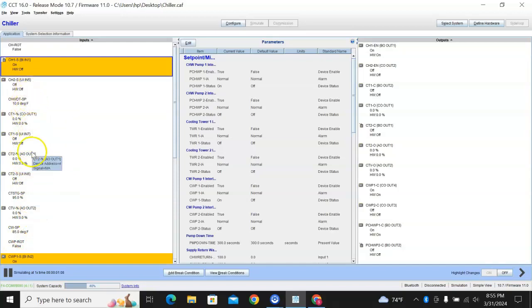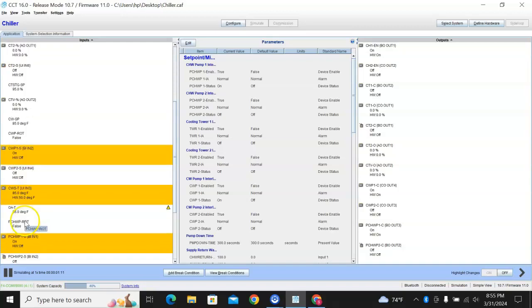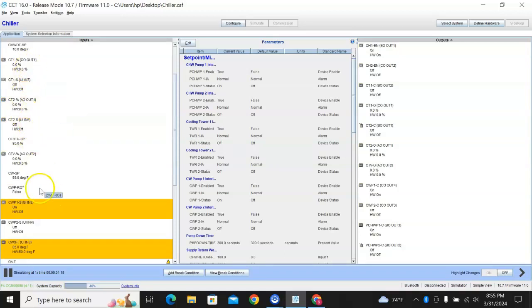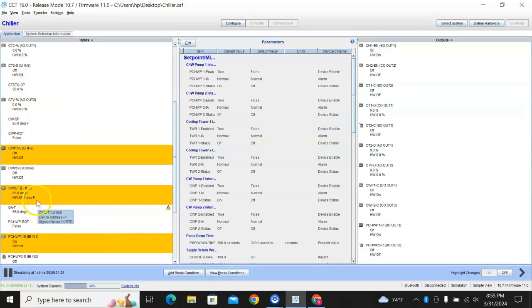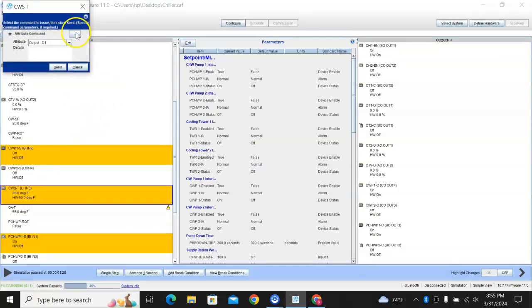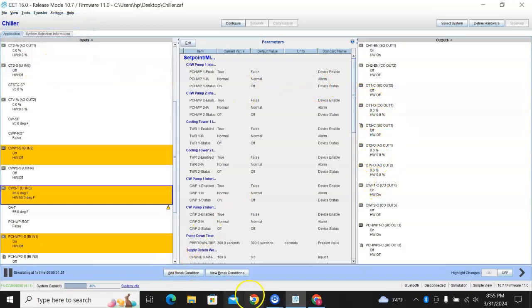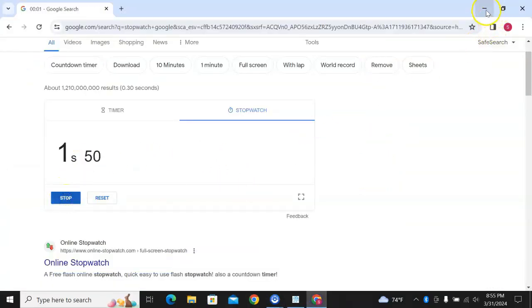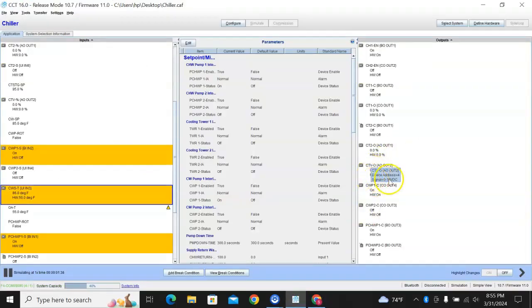Where is my temp? I'm going to slowly raise my temp. If I can find it. Condenser water temp. Right here. Okay. I'm going to go ahead and raise it to 86. And I'm going to go ahead and start that stopwatch. And then I'll come back to the stopwatch as soon as we're at least flowing water over the top. And I understand PIDs are slow. What I'm going to do is keep raising this temperature. Let's say it gets warmer. I'm going to do 87.